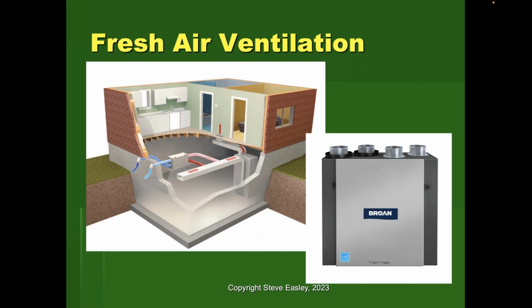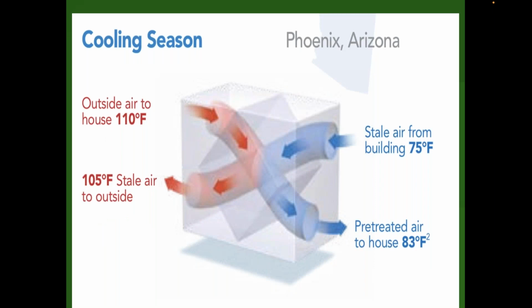Sure, and then I'm going to get into heat pumps and also talk a little bit about induction cooking and heat pump clothes dryers. I got some new info on that. So when I talked earlier about fresh air ventilation, it's required in almost all the codes today. And earlier I said one of the real things that would be helpful in electrification is to be able to have a very efficient ERV, but have it controlled by monitoring real indoor air quality. So these ERVs are energy recovery ventilators. They also have what we call heat exchangers, another term for heat recovery ventilation.